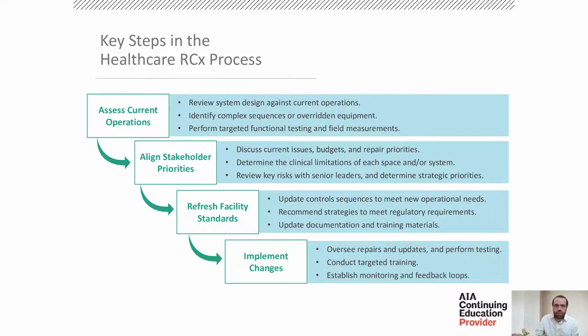This includes determining overridden equipment and finding broken equipment, and the third step is performing targeted functional testing and field measurements. This isn't the same as doing point-to-point testing and functional performance testing on an entire floor with a hundred VAV boxes. It's doing functional testing on the chilled water system or the boiler system, or looking at interlocks and similar things—finding the systems that are most critical and of highest value to a client, and testing just those systems.